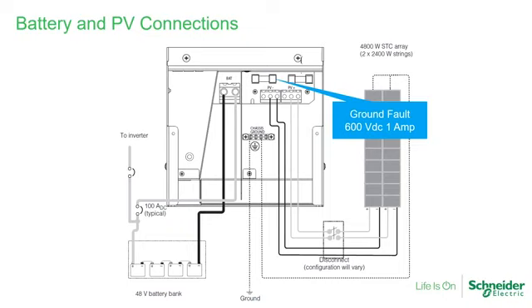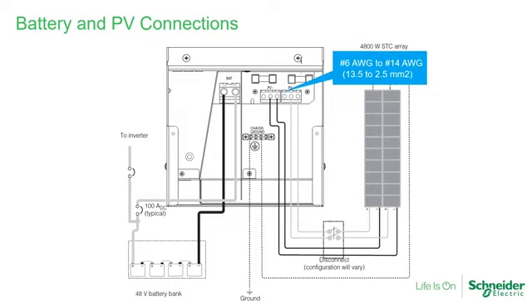What we're actually trying to detect is if there is 1 amp or greater in the ground, it will open the fuse and give you a ground fault. Some of the reasons why you may have a ground fault are damage on a conductor that has become loose because of wind, has been cut, or rodents maybe. I've seen birds' nests under arrays. With a cut conductor, you may have a conductor that is moving with the wind and the rain and is touching the array, the frame of the modules. Well, now I have current on the frame of the module. That's a ground fault. This is why, per NEC code, you have to have this fuse in place. And like I said, 99% of the time, this fuse will be on the negative side.